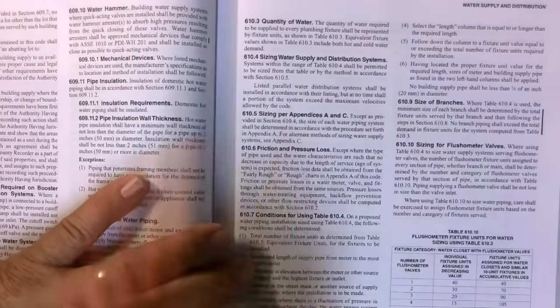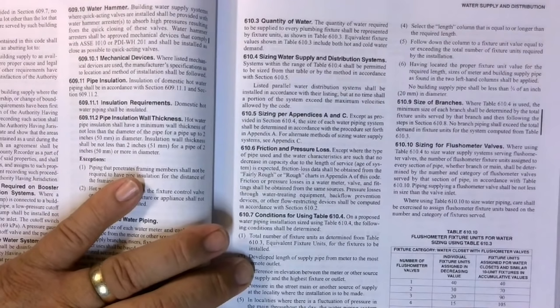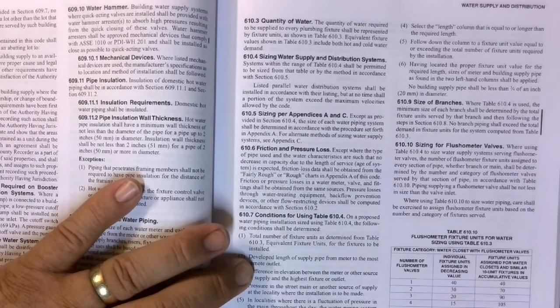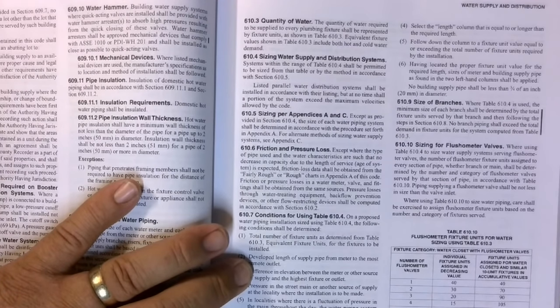Systems within the range of table 610.4 shall be permitted to be sized from that table or by the method in accordance with section 610.5. We'll get into 610.5 in a second. Listed parallel water distribution systems shall be installed in accordance with their listing, but at no time shall a portion of the system exceed maximum velocity allowed by code. So we cannot exceed our maximum velocity.